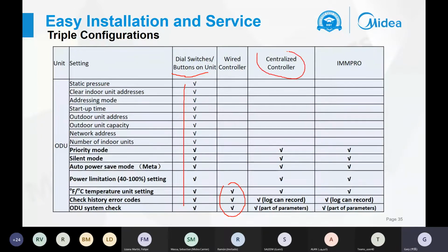And for the centralized controller, you can set more mode functions than the wire controller, like the priority mode, the silent mode, or the auto power save mode, just like the meta. Meta we mentioned before is the flow amplitudes. And IMMPRO can set the same functions as the centralized controller. The centralized controller has the same level in the BMS. They are at the same level in the controller sequence.